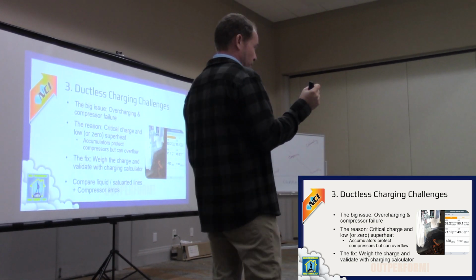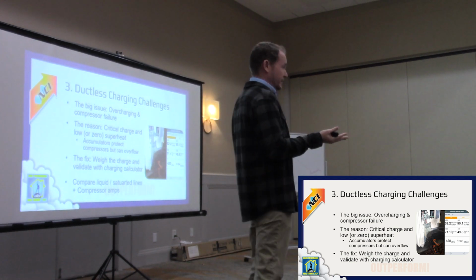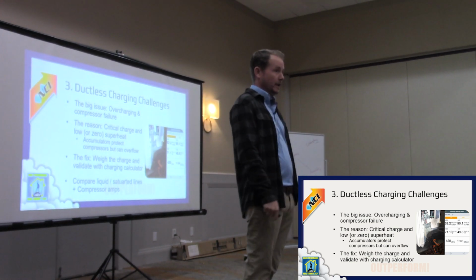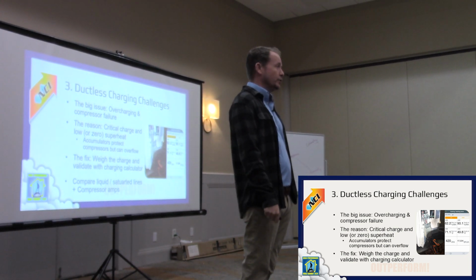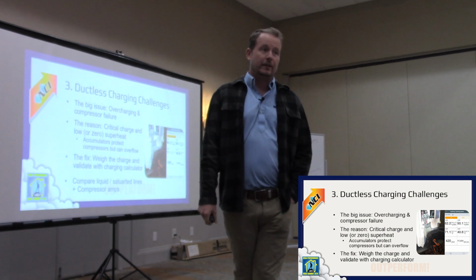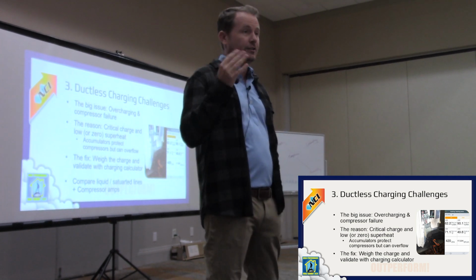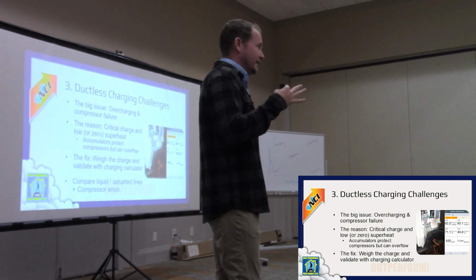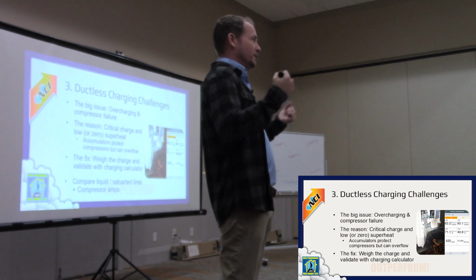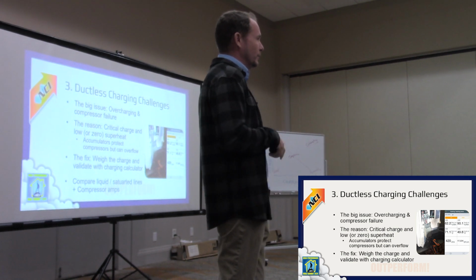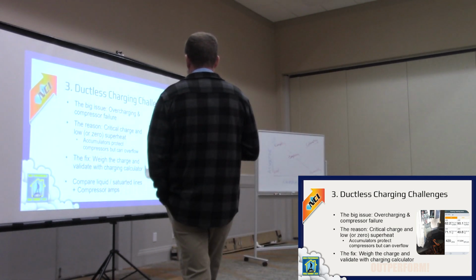Most ductless systems run near zero superheat, meaning the suction line coming back is nearly the same temperature as the evaporator coil, and they're just relying on the accumulator to keep liquid from making it to the compressor, which is another reason they're critically charged. You can overwhelm that accumulator if you keep adding more charge. Now they have algorithms in there so that when it starts to see a high compression ratio, the compressor will ramp down, but you don't want to rely on that. It's not good for the equipment.